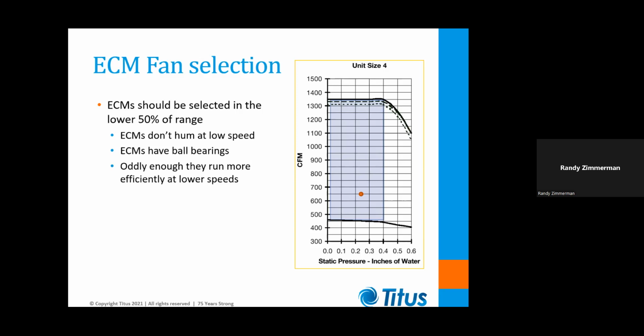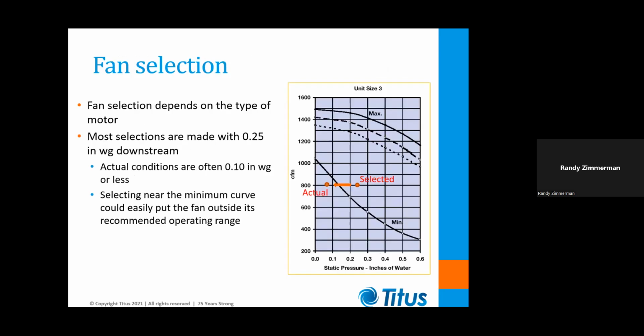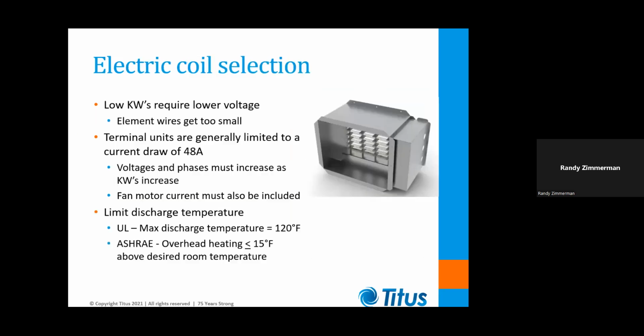I don't have to worry about burning up an ECM because they have ball bearings and don't have the low speed operating issues associated with the PSC motor. Now here's a problem that sometimes people run into where they select a PSC fan low. They'll select it at 0.25 inches and they'll say, hey, I'm on the safe side of that minimum operating curve. But then when the box actually gets installed and the operating pressure isn't really 0.25, let's say it's really less than 0.1, that can shift your operating point to the wrong side of the curve, and now you do have an operating problem. So that's why you never want to select PSC motors anywhere close to that curve, because there's always the danger that the actual operating conditions could shift you to the bad side of the curve.